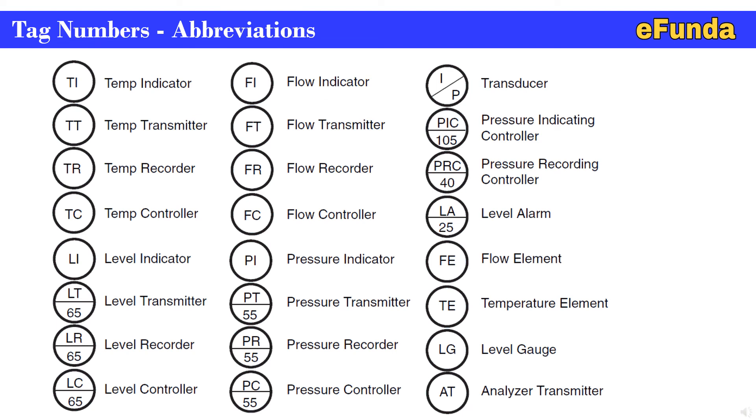Tag numbers abbreviation. Now we will glance through the abbreviations of the tag number. TI is temperature indicator, TT is temperature transmitter, TR is temperature recorder, TC is temperature controller. LI is level indicator, LT is level transmitter, LR is level recorder, LC is level controller.